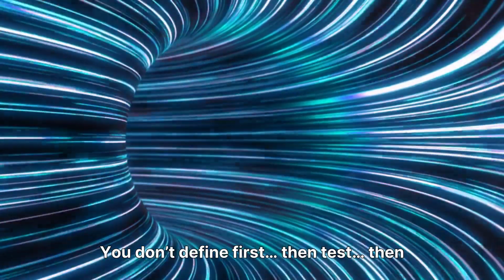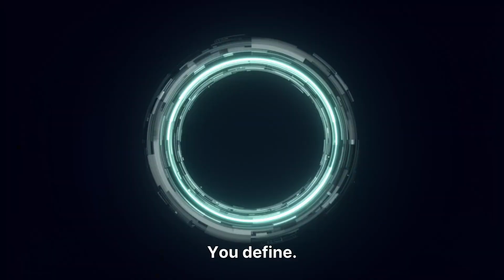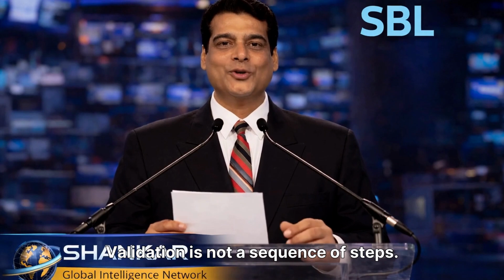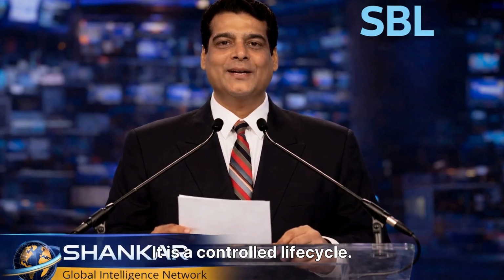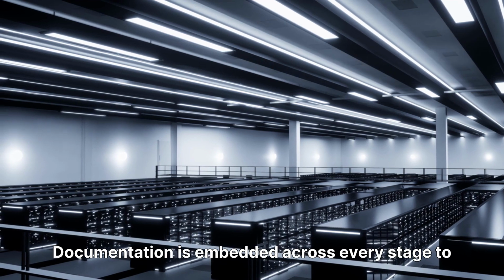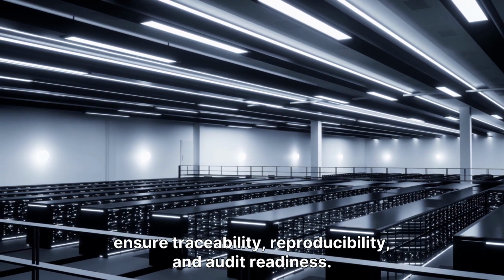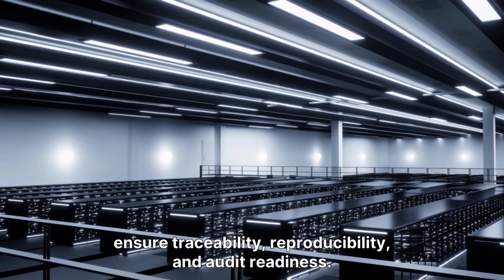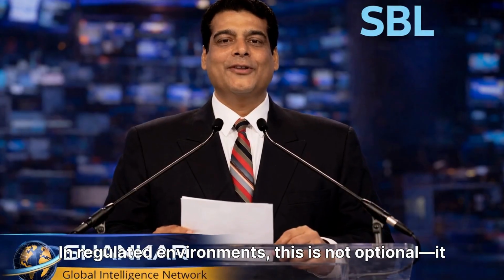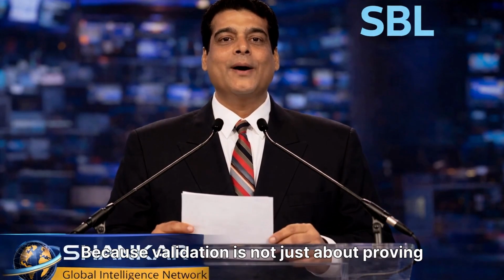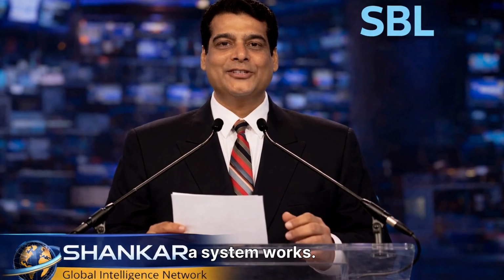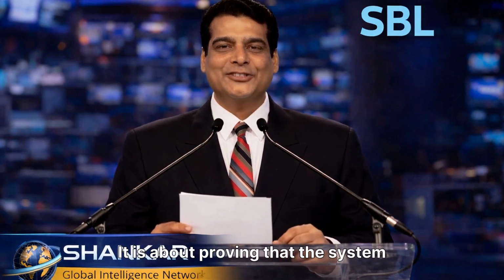Now let's go further. Validation is not linear. It is continuous. You don't define first, then test, then document. Instead, you operate in a loop. You define, you document, you execute, you record, you review, you trace, and then you repeat. Validation is not a sequence of steps. It is a controlled life cycle. Documentation is embedded across every stage to ensure traceability, reproducibility, and audit readiness. In regulated environments, this is not optional. It is fundamental because validation is not just about proving a system works. It is about proving that the system can be trusted.